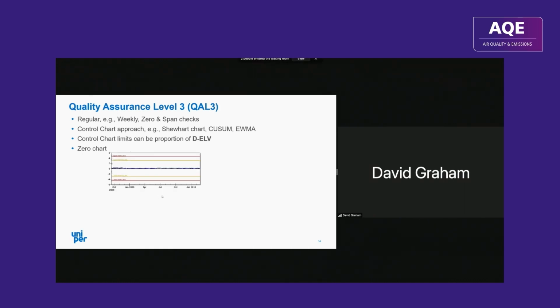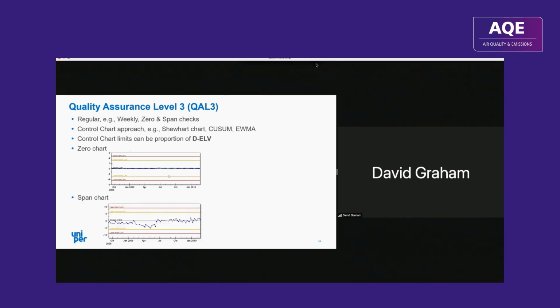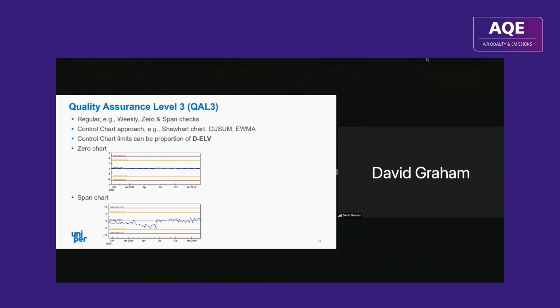fixed absolute uncertainty. And I'll just very briefly mention quality assurance level 3. So the drift is measured, say, on a weekly basis, plotted on a chart with warning and action limits, and the AMS is allowed to drift within those limits. So if there's a really good zero performance there in the top chart, you can see some drift here in the bottom chart, and around July 2009, in that case, it looks like something was done to the instrument, and that has been corrected. So that's the sort of use of QAL3.